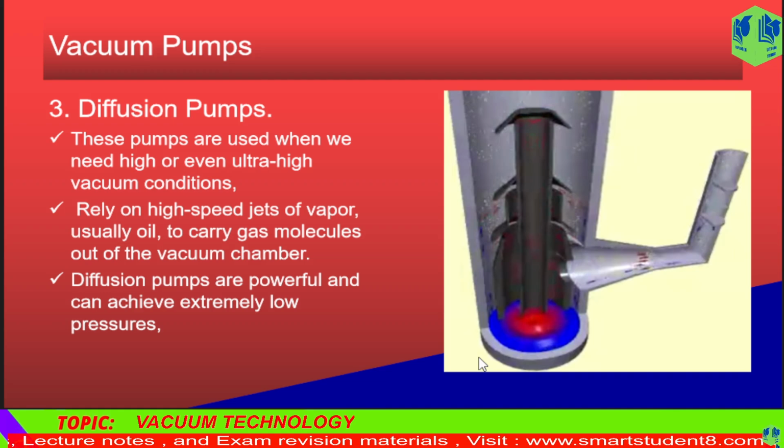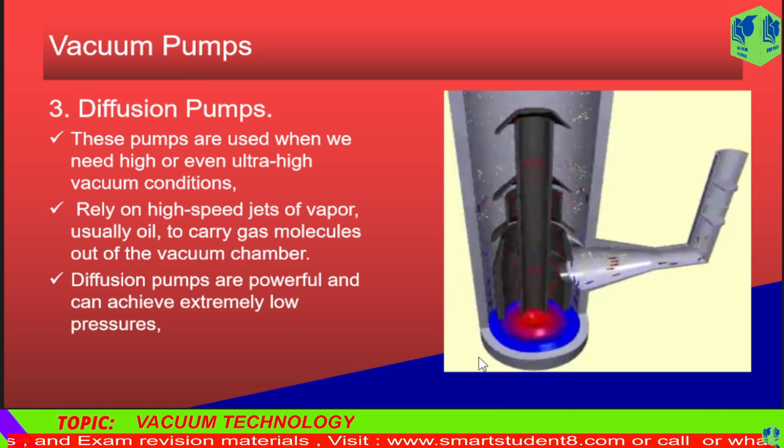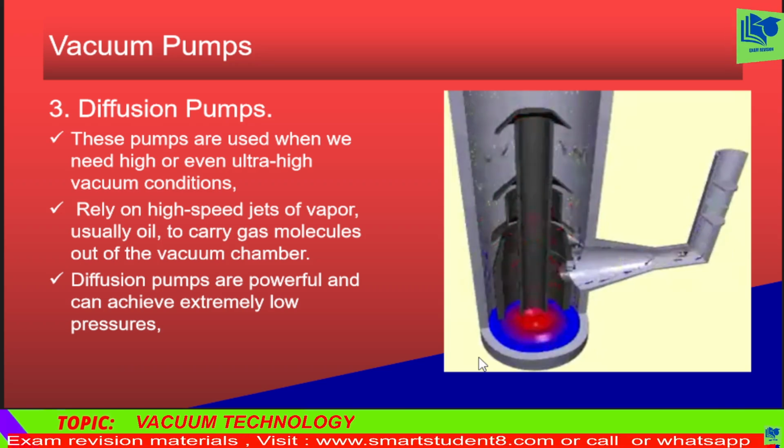Diffusion pumps are powerful and can achieve extremely low pressures, but they require careful maintenance and monitoring because the oil used in them can degrade over time.